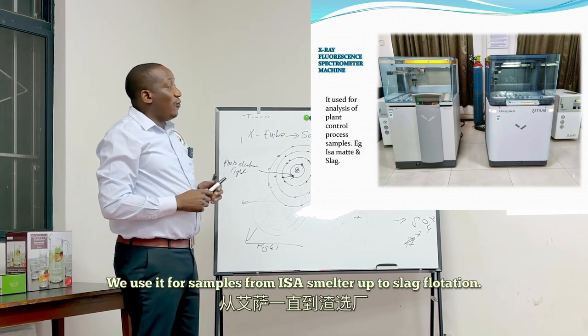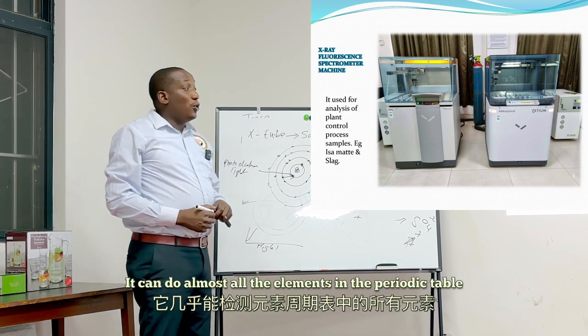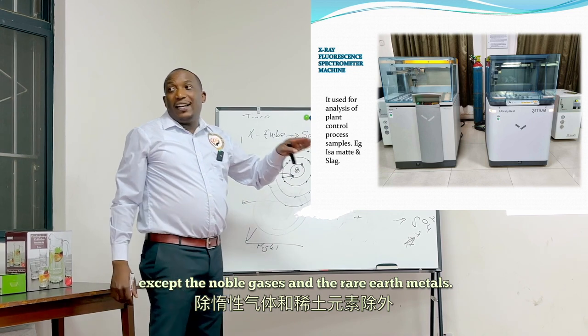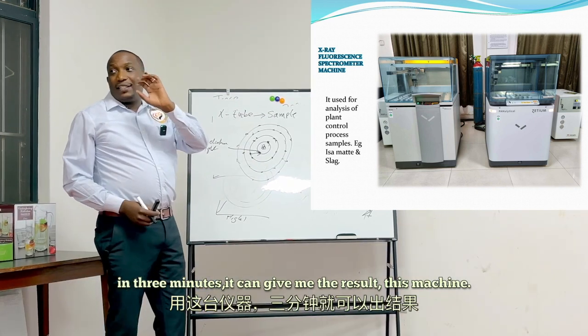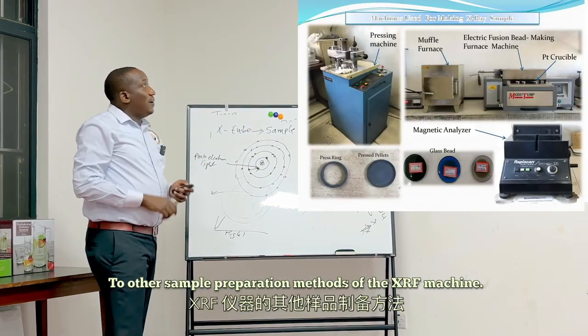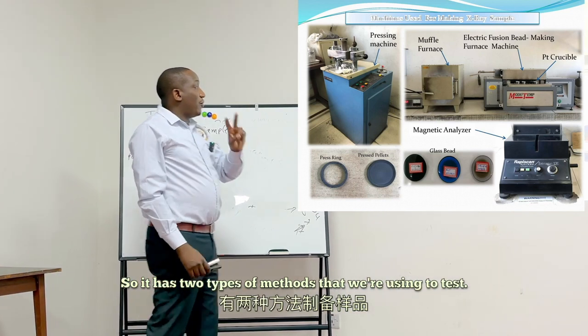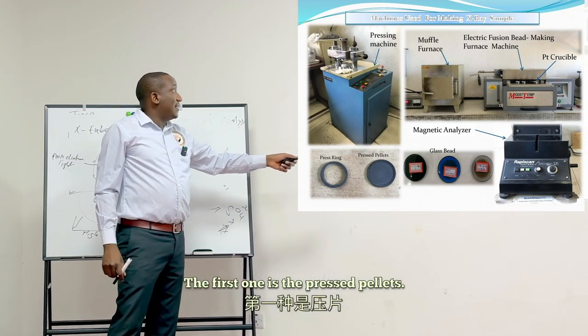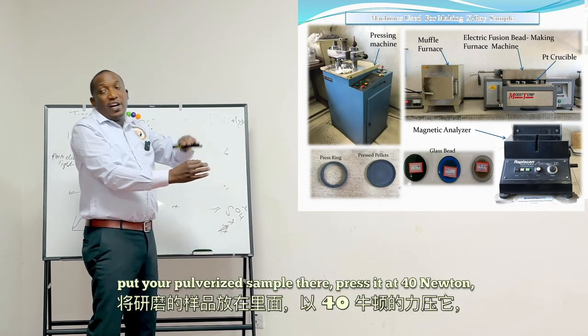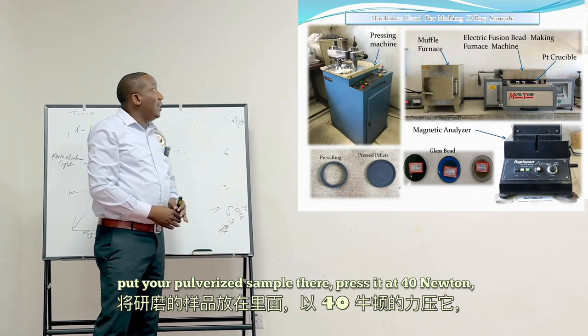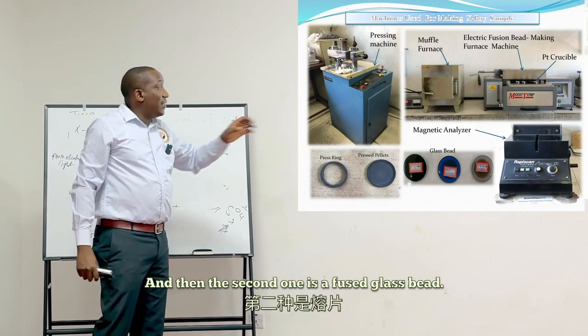The XRF is used for analysis of plant control processes — from the ISA smelter through to slag flotation. It can do almost all elements in the periodic table except noble gases and rare earth metals, and gives results in three minutes. It has two sample preparation methods: the first is pressed pellets — you get the ring, put your pulverized sample in, press at 40 Newtons, and get a pellet that the XRF can analyze. The second is a fused glass bead.